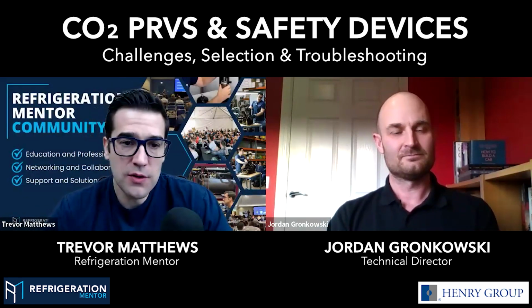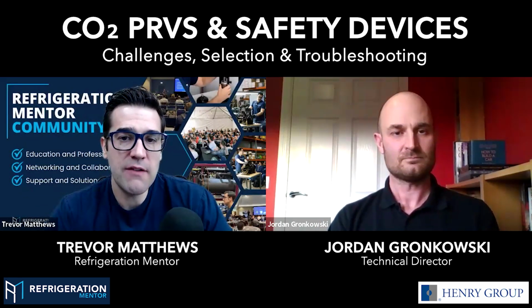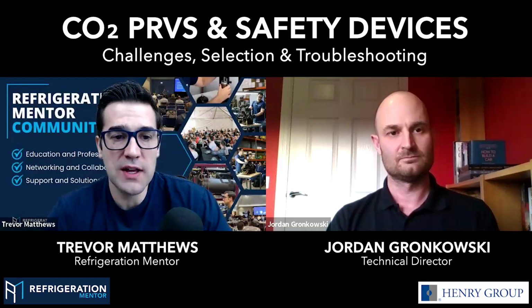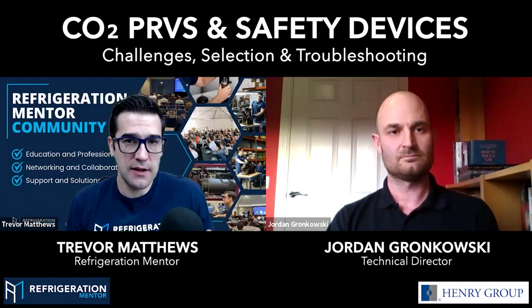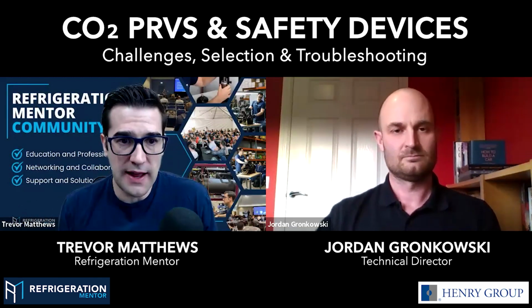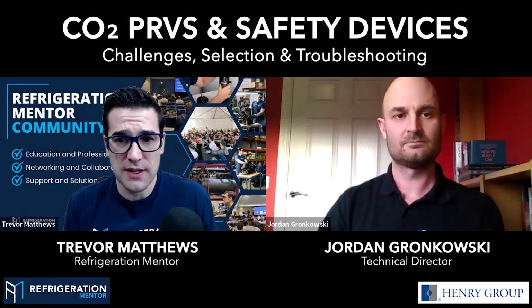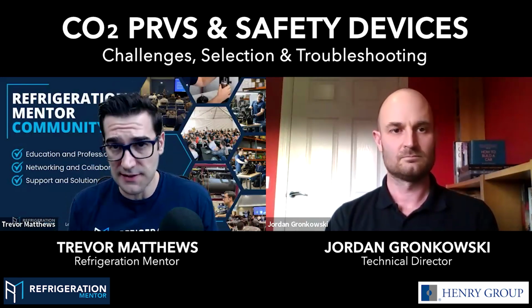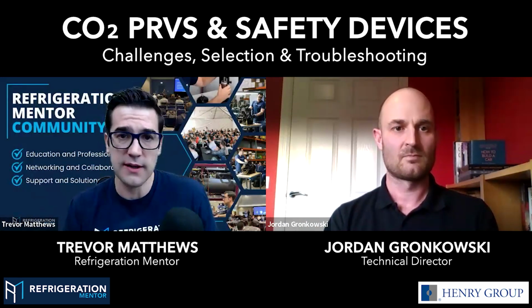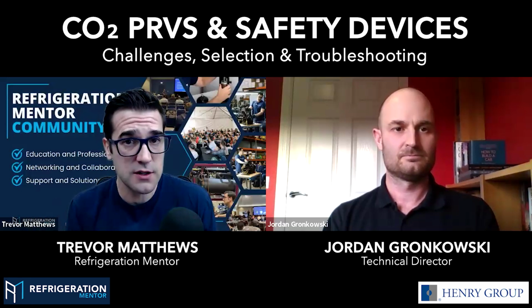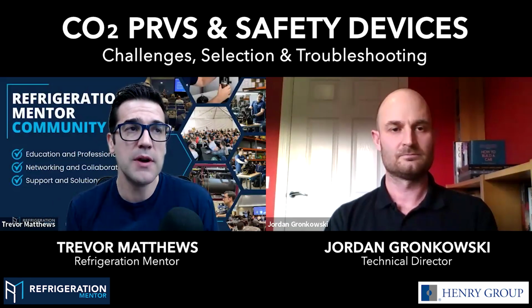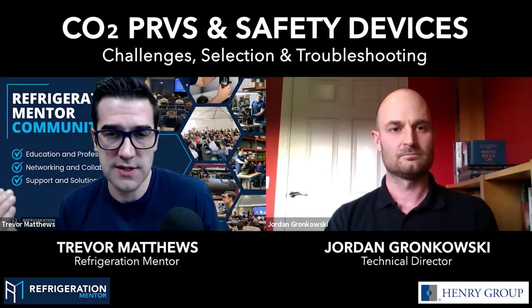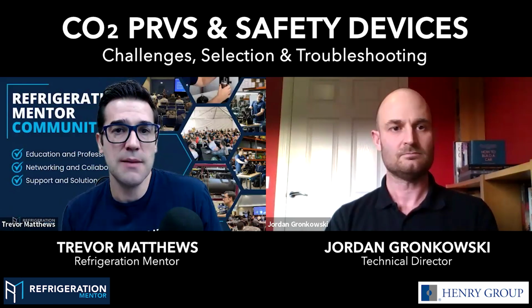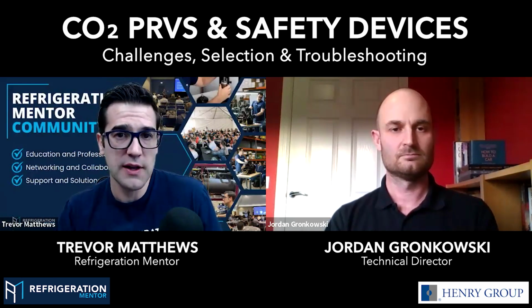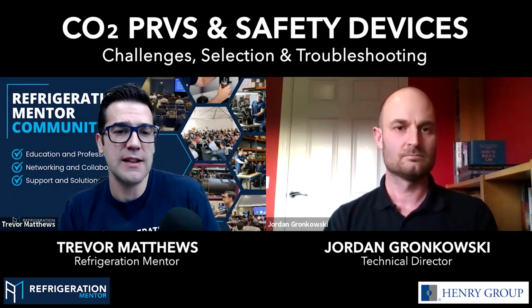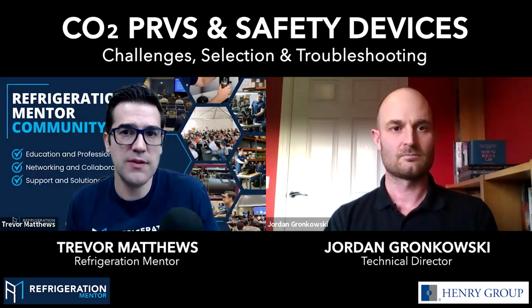And we might get into it in some of the slides you have, but let's talk about that right there. If you have an oversized valve, because in Canada here, our B52 code states that after every 5 years, I believe, they need to be inspected or replaced. And I think that's around the world, it's a similar code. So you need to understand the code in the country you're in. But if all of a sudden you need to replace it and you see it there, and they put one that's too large on, and because you just said it may work erratically, what if someone puts a too large PRV on a system?